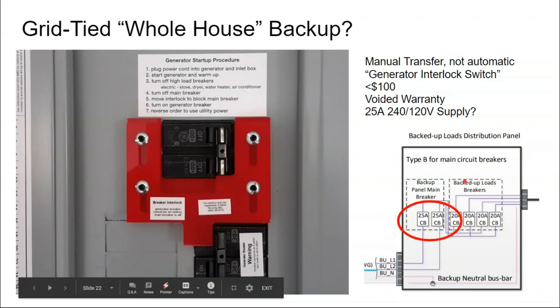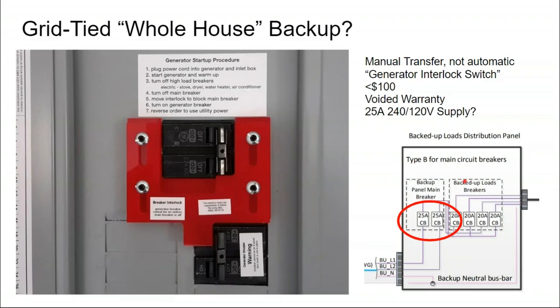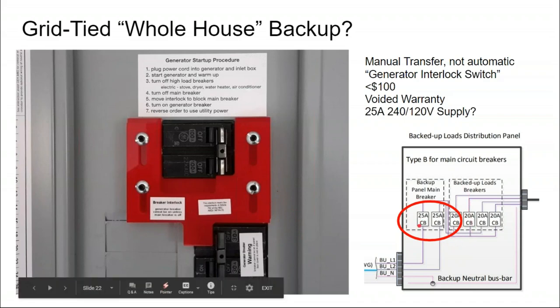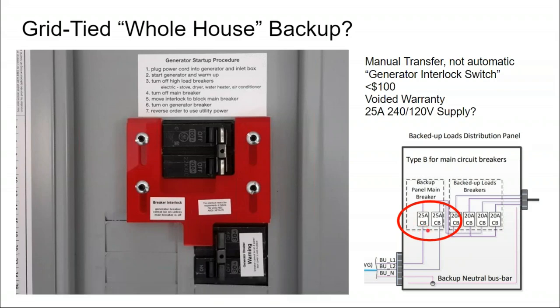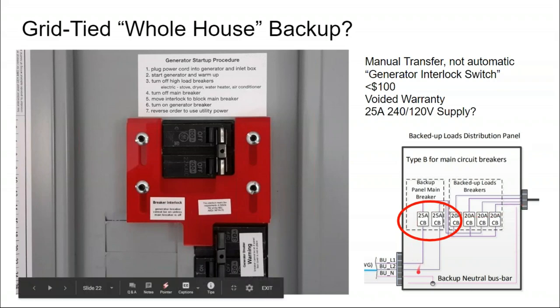For example, the SolarEdge StorEdge solar inverter is a grid-tied battery inverter, and it only backs up a 25 amp circuit. And of course, that could actually back up multiple circuits provided they don't all run at the same time. But if more than 25 amps per pole gets pulled through this breaker, your backup loads all stop because the breaker trips.